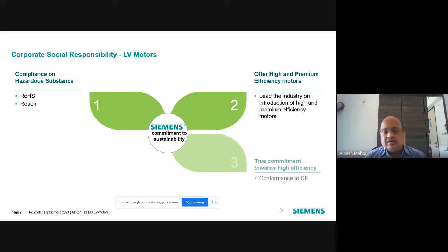I had the opportunity to listen to eminent speakers talking about IE3, IE4 motors. So what exactly are IE2, IE3, IE4 motors? These are classifications driven by IEC and Indian standards, which allow a manufacturing tolerance, and that tolerance can be as high as 15% of the loss.